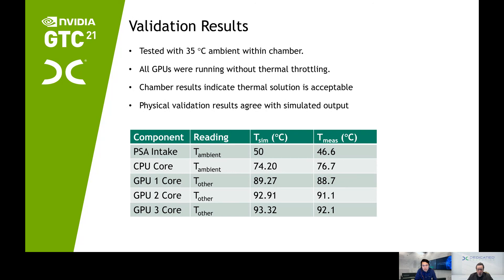GPU one was simulated at 89 and came in measured at about 88. GPU two is in alignment where it's at 92.91 simulated and the measured is a little less. GPU three as well — 93.32 simulated and the measured is 92.1. It's important that when building simulated models we're not always going to get everything right, so we have to go back to the block models in IcePak to modify them so that they come into alignment with the real world. But the benefit is that you can reuse these block models over and over and speed your development effort.